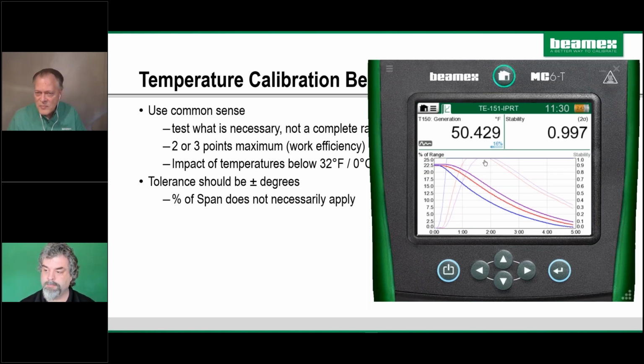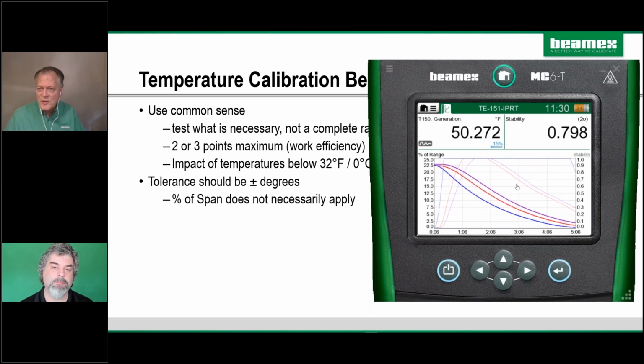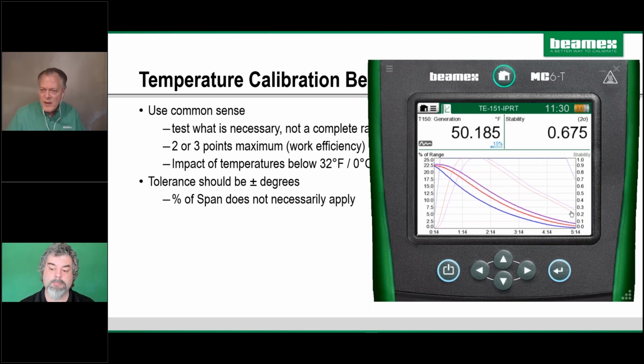But I also want to mention that Beamex is also calculating a stability factor. So the internal reference has just now appeared. It's not very stable compared to the field probe and the reference probe that are in the insert, so they're just kind of trucking along, trying to catch up.